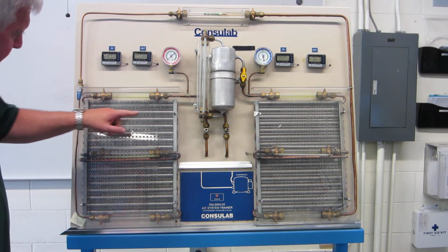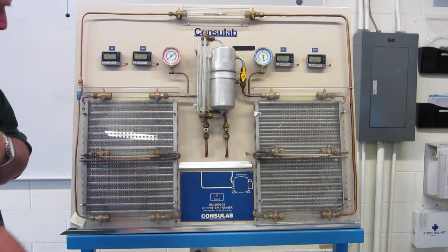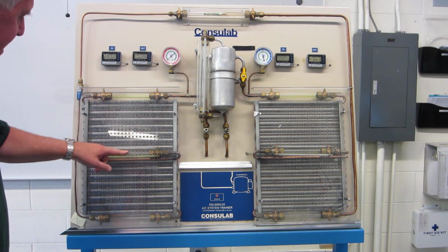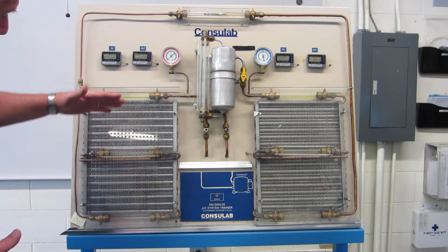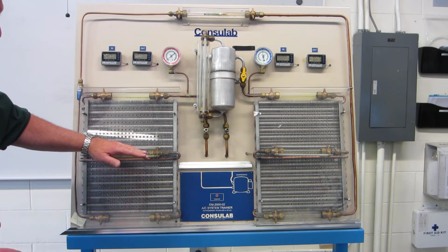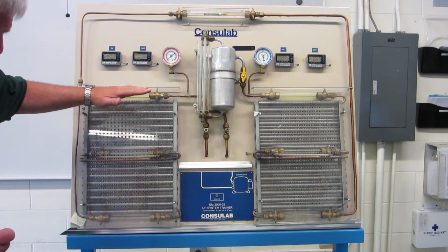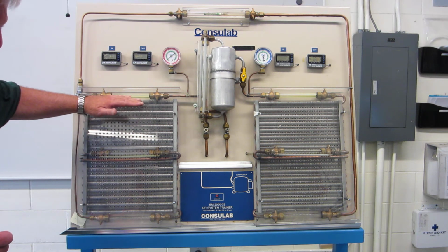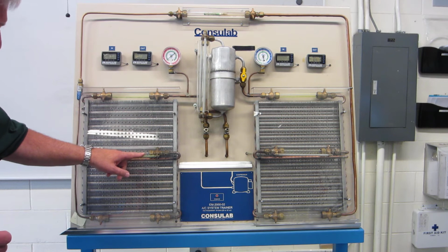And as it goes back and forth through the condenser, and ram air, or the condenser fan, as I mentioned before, pulls that heat energy out, we get latent heat of condensation. In other words, we go from a vapor back to a liquid. So we have a change of state taking place with no change in temperature. We have that hidden heat again. So as you look at the board, you'll notice again now that you'll start to see vapor and a liquid.